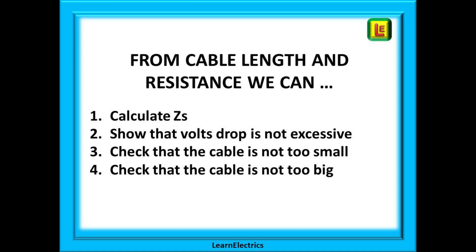Knowing the length we can also calculate the voltage drop to show that the voltage at the point of use is enough for the equipment to work normally. We can also confirm that the cable is not too small in size that it represents an overheating danger and a possible cause of fires. The opposite of this is that the cable size is much bigger than it needs to be in which case you or the customer are paying a lot more money for the copper that you do not need.